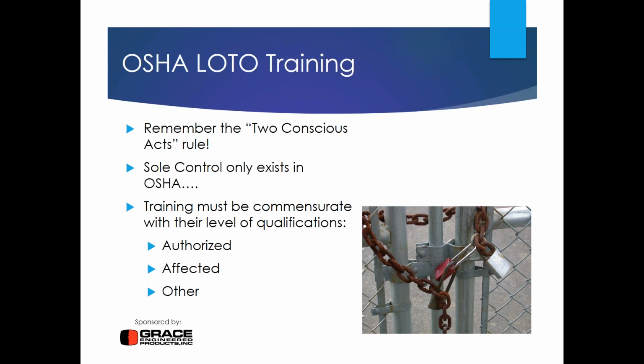So when you apply this to the idea of lockout, tagout, the general idea is that in order to have an energy release, you're first going to have to cut my lock off if you were going to energize the circuit I was working on. That is both excessive and purposeful. You're not going to accidentally cut somebody's lock off. And then you must do another conscious act, and that would be to reset the device or close the device that energizes the circuit.